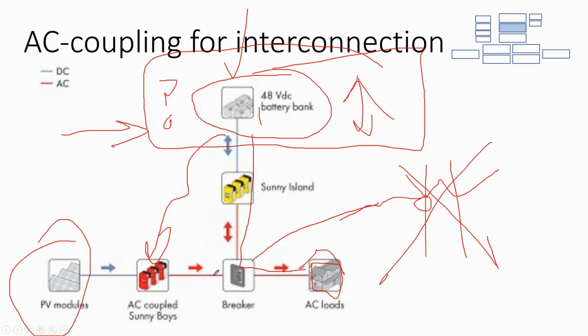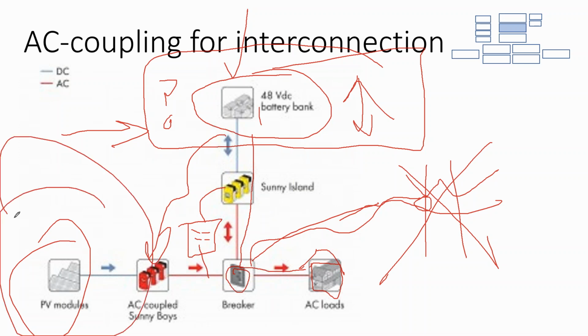So often you have to go and put in a separate critical load panel because this panel is connected to the grid. And you don't put in a critical load panel just to protect critical loads. I mean, really, you want to power your whole house. It's inconvenient just to have your refrigerator running or your air conditioner running when you could be providing a whole house worth of power. You'd want to power your whole house.